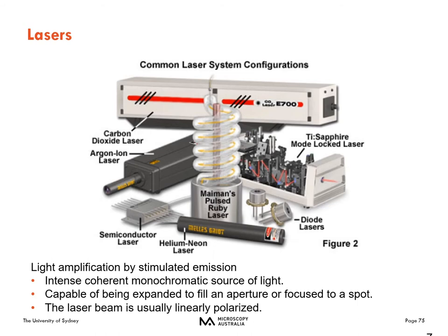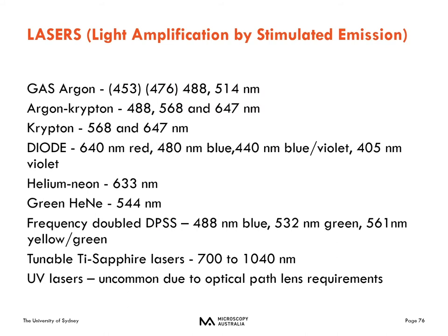Laser beams are typically linearly polarized, but I'm not going to spend much time on that. What are some typical lasers available? For example, the gas argon laser has multiple laser lines — typically people use the 488 and 514, and occasionally the 453 and 476. There's an argon krypton laser, just the krypton laser. More and more common now are single wavelength diode lasers: a 440, 480, 640, or a 405 for your DAPI probes. The helium neon for farther red probes — the 633 line.